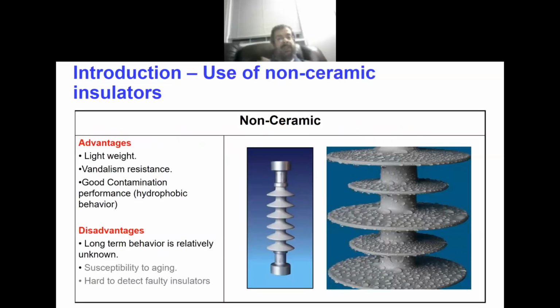Let's start with non-ceramic insulators. They have completely opposite properties compared to ceramic insulators. The first obvious property is lightweight. For example, in 400 kV insulators, we can reduce the weight by 90%, which is a huge reduction in mechanical burden. This is a big advantage.